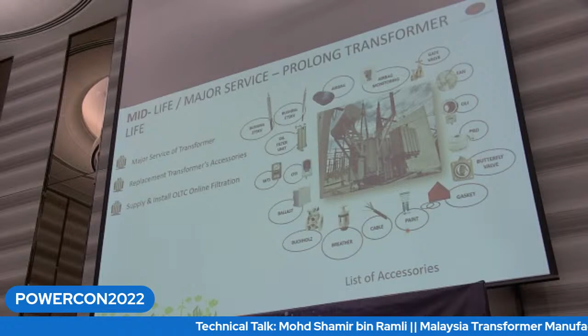In addition, we also look at digitalization. When we replace the accessories, we replace them with a newer generation of accessories that can communicate digitally with the IEC 61850, with a digital substation that will give you visualization on the transformer. So again, it's all about visualization and data collection. And this data is stored in Tenaga's database for future planning and also asset monitoring.